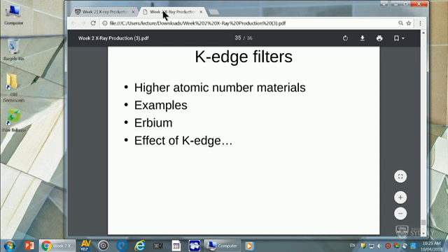What we're trying to do every time we X-ray someone is match the X-ray beam to the K-edge of the characteristic or the substance you're looking at within the body. Also, you'll notice in this beam is instead of this very broad X-ray spectrum, we've now narrowed it a fair bit. So no longer is it as crude as it was. So now it's going to be easier to match this to whatever you're looking at in the human body than matching all this stuff, you know? So it refines the X-ray beam spectrum effectively as well.